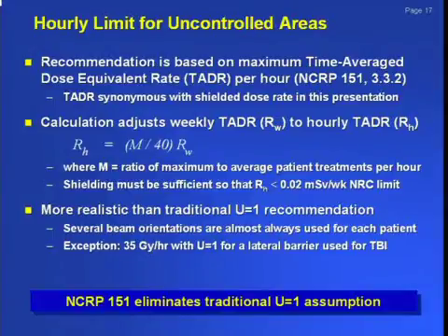What you do have to be very careful of is that your hourly limit for uncontrolled areas is not exceeded. The recommendation is based on your maximum time averaged dose equivalent rate. And if that's not a mouthful, I don't know how to say it. But the TADR is synonymous with what we have traditionally referred to as the shielded dose rate in this presentation.